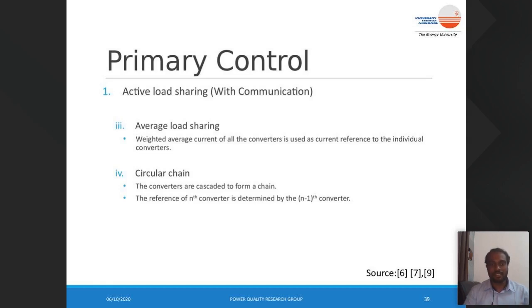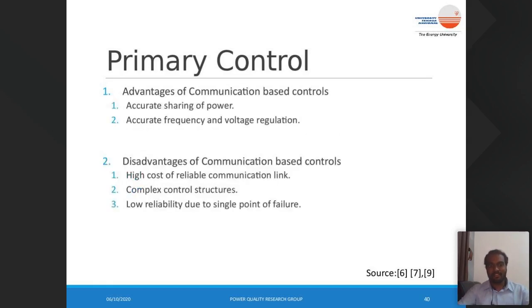And finally we have circular chain control, where, suppose we have n converters, the n minus 1th converter determines the current reference for the nth converter, where all the converters are formed as a chain to control. The major advantages of these communication-based controls are accurate power sharing, which results in accurate frequency and voltage regulation, but it results in high cost for a reliable communication link, and it also requires complex control structures.